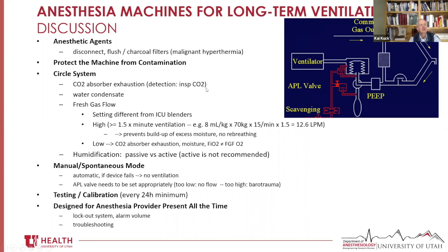CO2 absorber exhaustion. Oh, that's right. You need to make sure you have an inspiratory CO2 alarm that's set, because if you run on low fresh gas flow, you're going to exhaust the absorber eventually, and then you need to replace it, something ICU people are not used to because they don't have these. You detect that by looking at the inspiratory CO2, so you need an alarm for that and need to make sure that it's appropriately set.